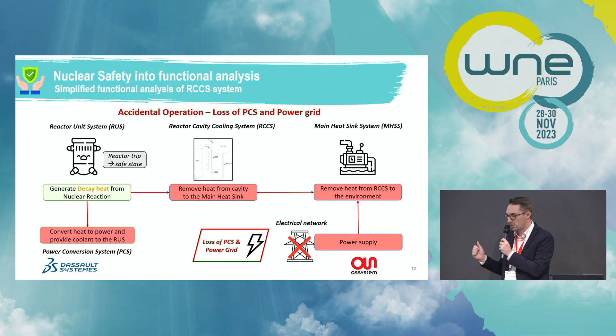So the whole system needs to be reconfigured. For example, to mitigate this scenario, we need a backup cooling tower to remove heat from the RCCS to the environment, and this backup cooling tower is power-supplied by an emergency diesel generator. In this situation, the reactor cavity cooling system has to remove all the decay heat from the cavity to the backup cooling tower, so the heat load is quite different.